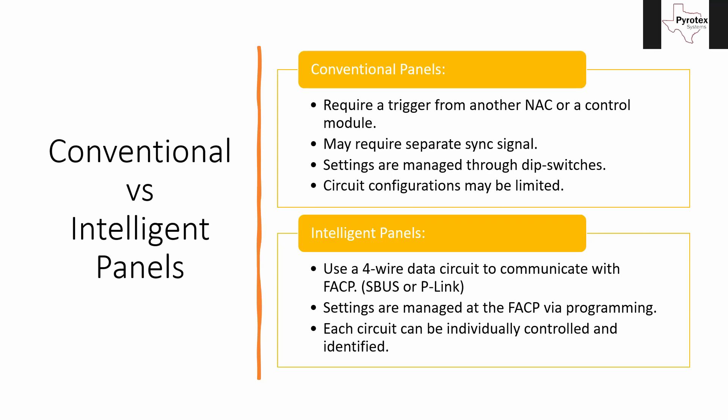All the settings in the intelligent panels are managed through the control panel via programming — there are no dip switches for that on board. The only dip switches on most of these intelligent panels are just to set the address so the fire alarm control panel knows which power supply or amplifier this is. In that programming, each circuit can be individually controlled, configured, and identified.